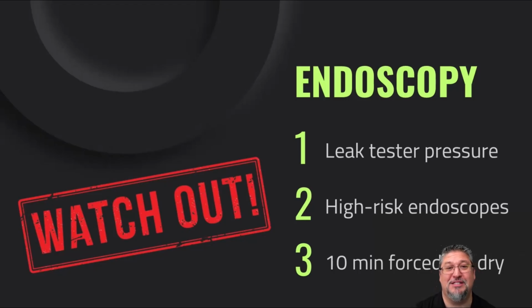Another thing that changed was the 10 minutes of forced air dry. A lot of people think, well, I don't have to do that because it's going to hang in the cabinet. No, it's still a required step before it goes into the cabinet, that 10 minutes of forced air dry. The reasoning is because a lot of people were getting droplets that were stuck inside the scopes. And because of how small the channels are, it's very difficult for drip drying or for gravity to work on them. So the scopes were just staying moist inside. And of course, anywhere where you have a dark, damp environment, you're going to have microorganism growth. So a lot of these outbreaks that we were seeing from endoscopes had probably some kind of connection to the fact that these scopes were hung wet. So make sure you're doing that 10 minutes of forced air dry.